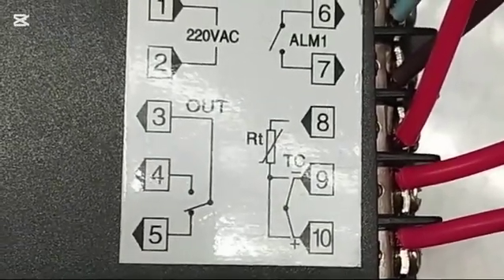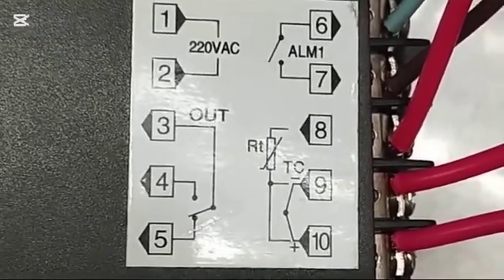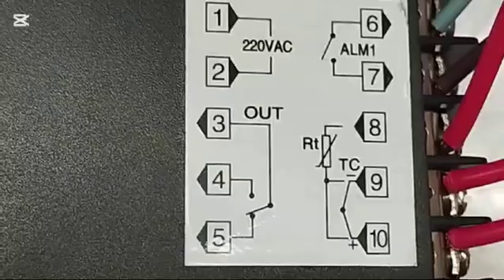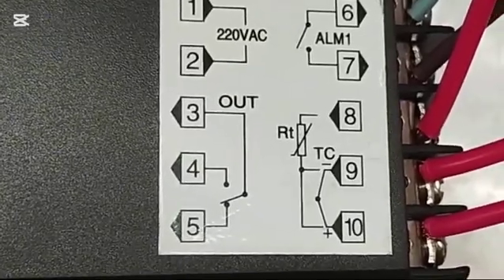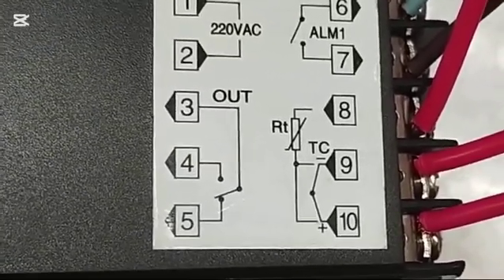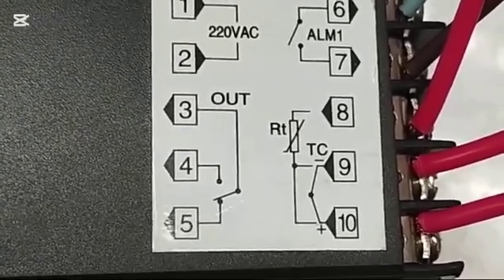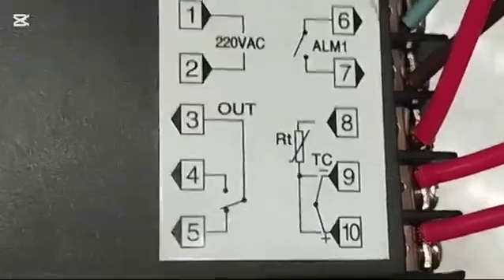1, 2 supply voltage 220 AC. 3, 4, 5 relay out. 6, 7 alarm. 8, 9, 10. Thermocouple temperature sensor connection. 10 positive, 9 negative.